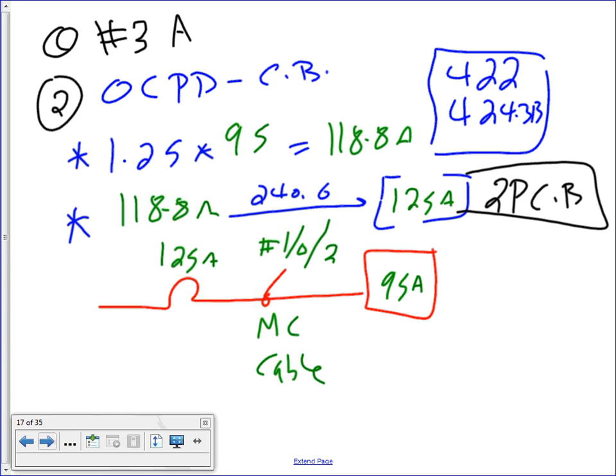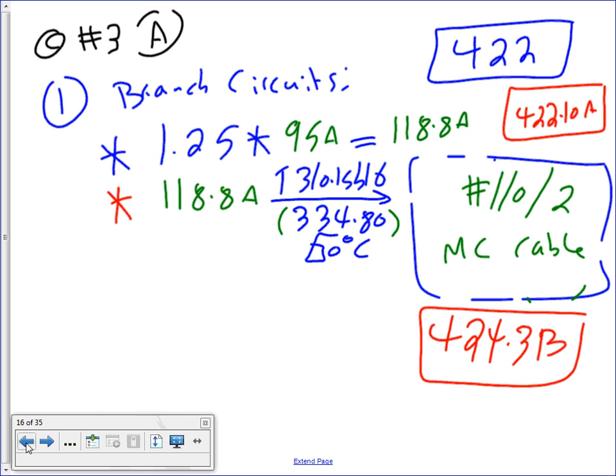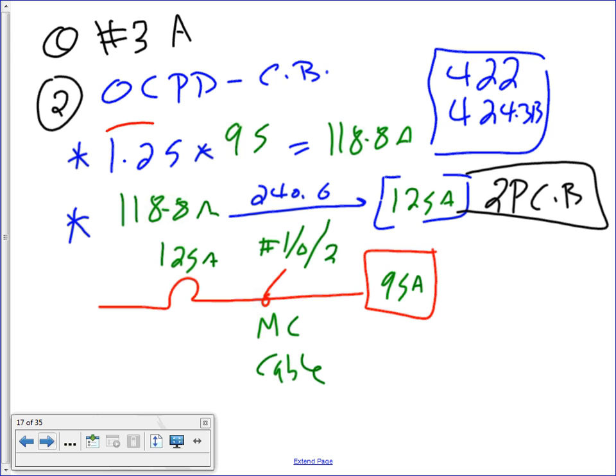If you want to do the check, since we used 1.25, guys, do I need to check? When do you check? Let me tell you why. What's the multiplier that you guys use for the branch circuit? 1.25. What's the multiplier that we use for the overcurrent protection device? 1.25. If the multipliers for the two of them are the same, there's no need to check because we use the same number. The one before, where we did the check, anybody know why we did the check? Because we used 1.5 for the overcurrent protection device and 1.25 for the cable. So you need to make sure that they match for appliances. In this case, no need to check. If you guys want to go check, can number 1/0 carry 125? Definitely does, at the 60-degree column. That's what we sized it at here. We sized it before, so there's no need to check for the cable.